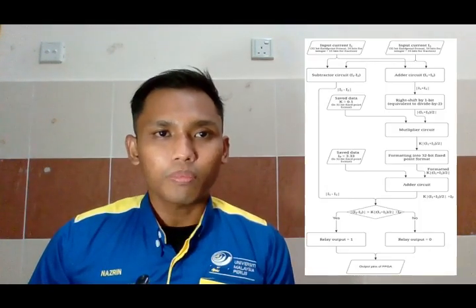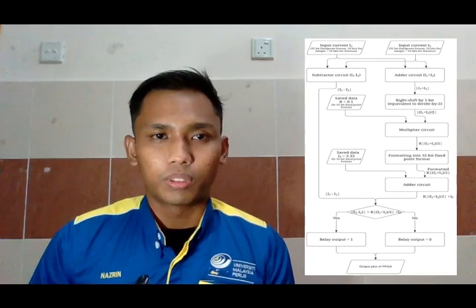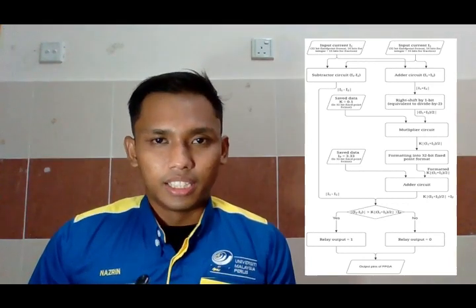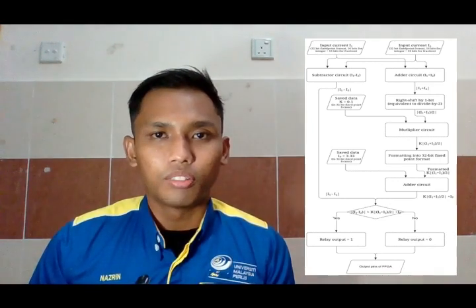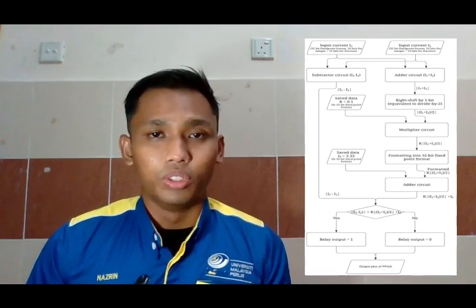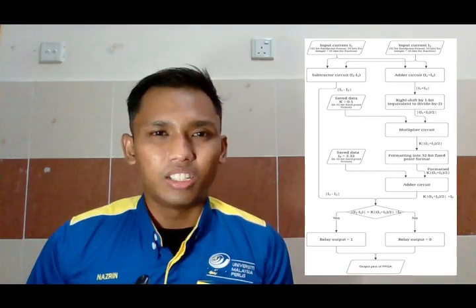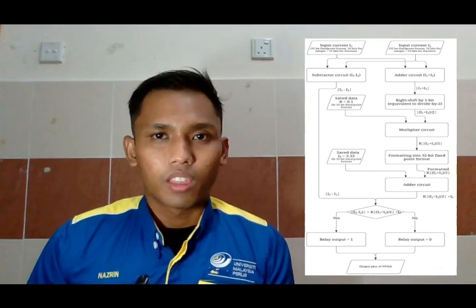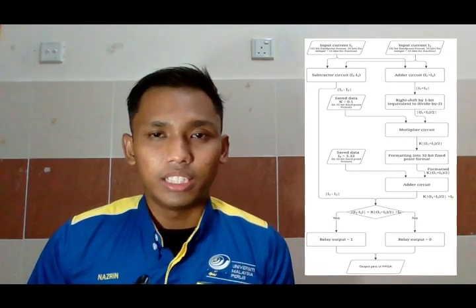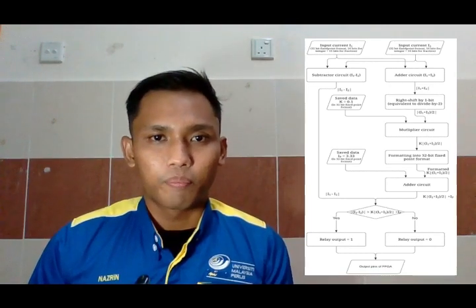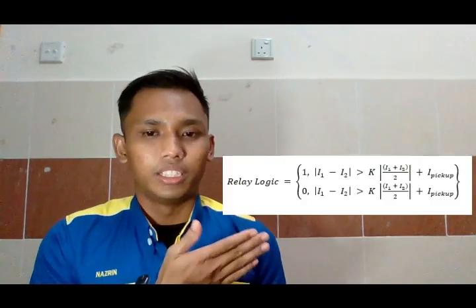Okay, for step 1, the most important and challenging step in the process is to design and code the relay. The relay's main task is to distinguish between internal faults occurring within the defined protection zone and external faults that happen outside this zone. When an internal fault occurs, the relay logic is programmed to be 1, indicating that the relay should operate and trip. On the other hand, during external faults, the relay logic is set to 0, meaning that the relay should not react. To summarize, the relay logic is carefully designed and coded in the field programmable gate array, ensuring that it follows the prescribed behavior as described in the equation above.